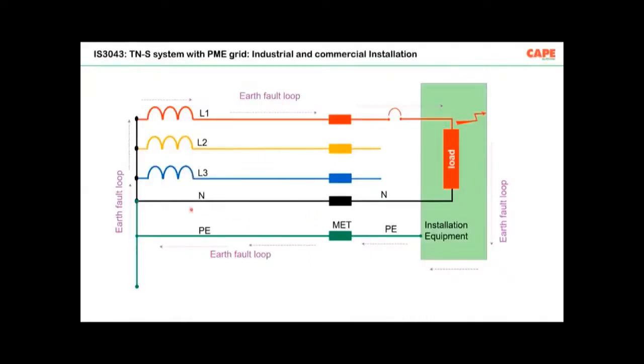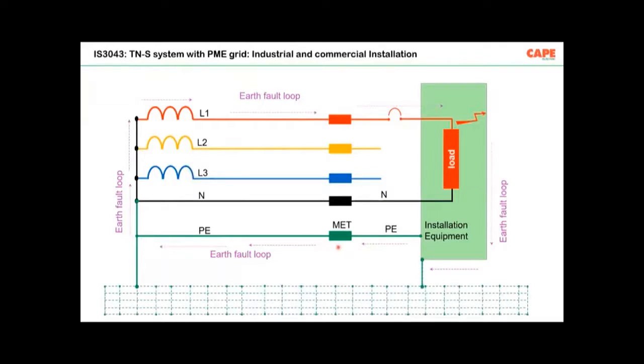Now, IS 3043 recommends a system called the TN-S system for industrial and commercial premises, with PME. What is PME? In large installations, you are sometimes unable to create a very low fault loop impedance path. As a result, your protective device may not work. To solve the problem, you make an earth grid, interconnect the neutral of the system, and connect the extraneous conductive parts of the installation so that you have an additional path for the fault current to flow back to the source. So automatically the fault loop impedance is smaller, and you get efficient disconnection of the supply. This is what is explained in IS 3043.